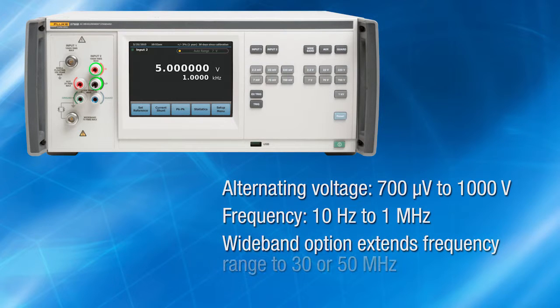A wideband voltage option extends the frequency range to 30 or 50 megahertz to meet the calibration requirements of Fluke Calibration 5700A, 5720A and 5100 series wideband options.